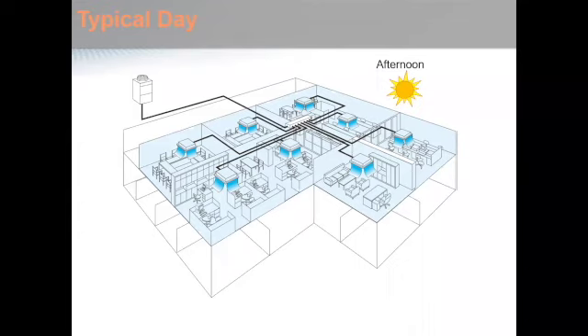So all of your zones can be in either heating or cooling, but the main difference with heat recovery is that each individual zone is going to be able to go into either heating or cooling on demand. So really, it's very similar to the heat pump technology that we discussed earlier. The only difference is that each zone can then transfer into heating or cooling as needed.